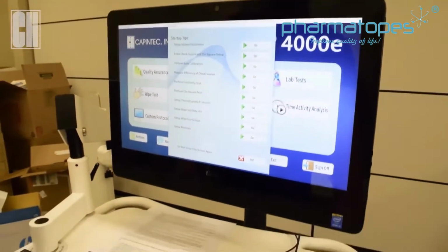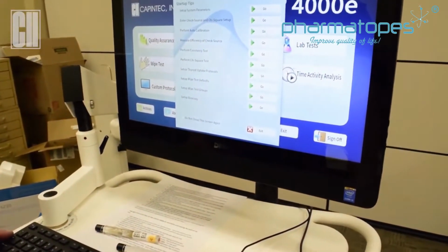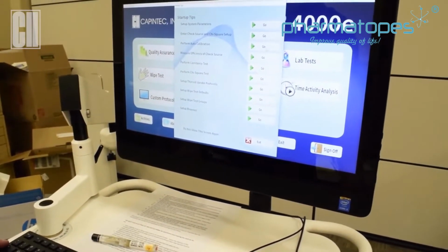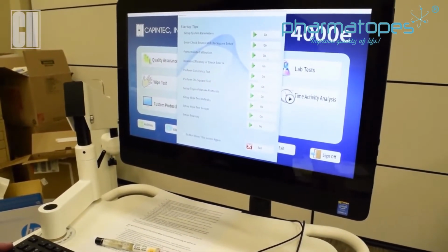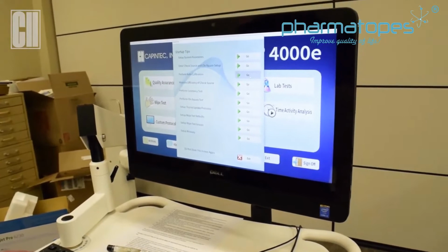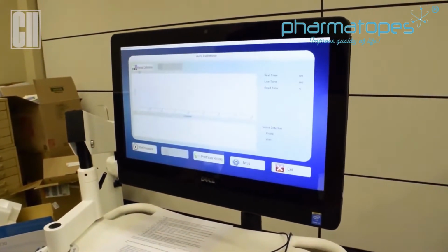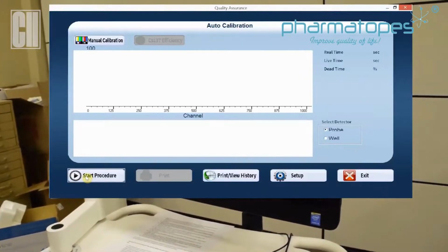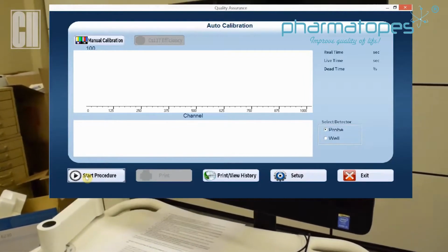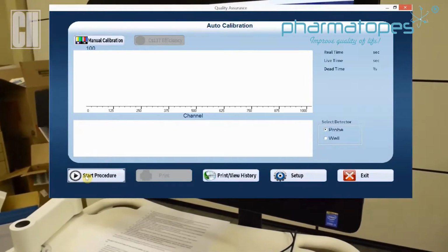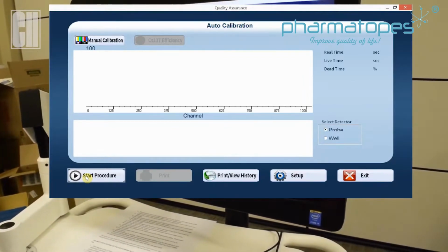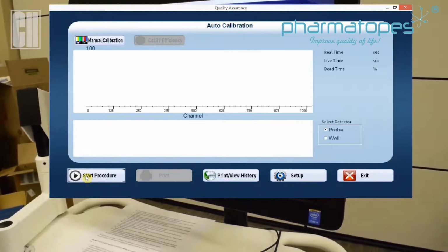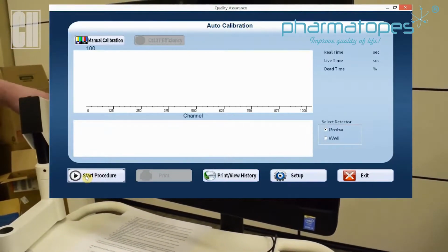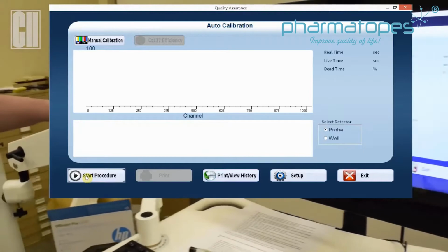Set. You can click on done. And now we can perform the calibration to make sure we're getting successful calibrations on both detectors. So we'll click on that. And here will be your main screen for doing your calibration. You have your option over here with which detector you'd like to calibrate. And then once you decide what detector you're calibrating, we're going to do start procedure.